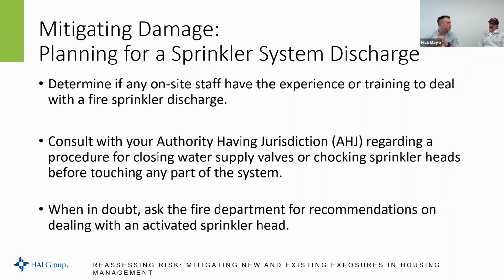Now, there is a caveat to that. We would most certainly be fine with mitigating the loss and having somebody shut down the valve. But this can't be an in-house only thing where, like Nick says, Mrs. Jones hits the sprinkler head, the water starts flowing, the maintenance man comes and chocks the sprinkler, stops the water, takes care of the mess, and doesn't let anybody know. There are codes that come into play where if that sprinkler head is going to be down for more than 4 hours, we need to know about that. Nick's side, the fire suppression side, needs to know about that, because if something else happens within that period of time and Nick's on the truck and says, oh, this building is sprinklered, and they get there and the sprinkler system's down, that's just going to open up a whole new world of problems.